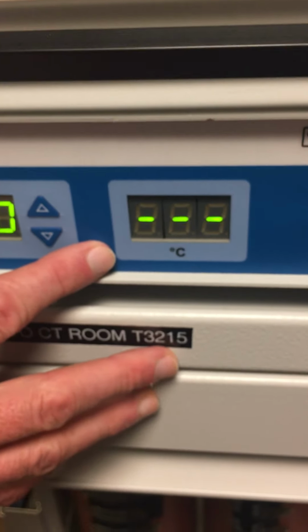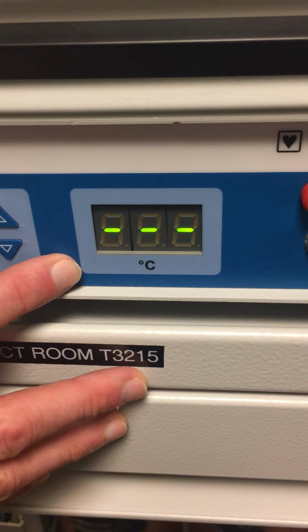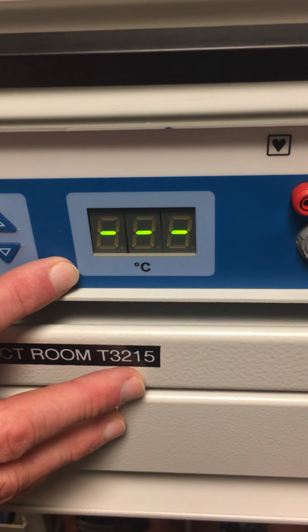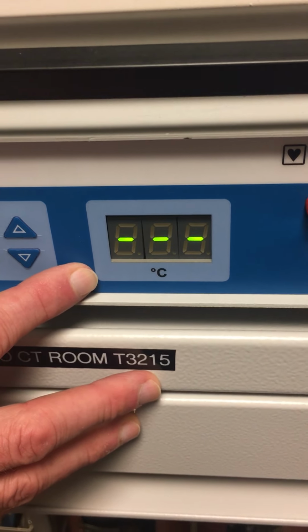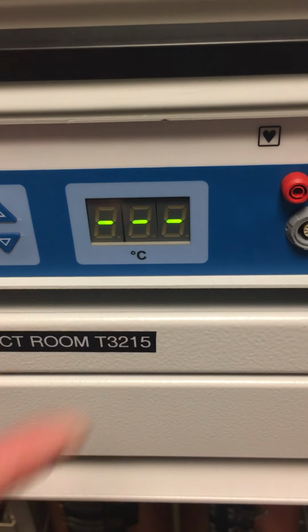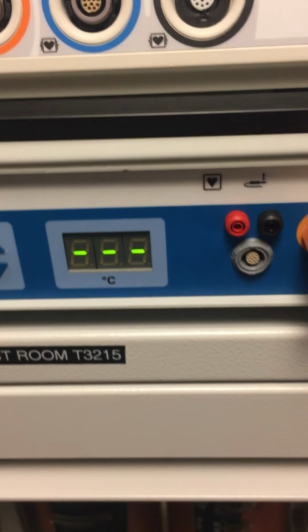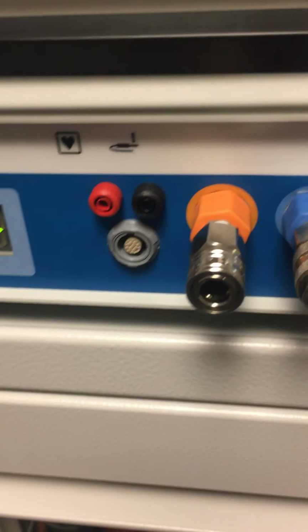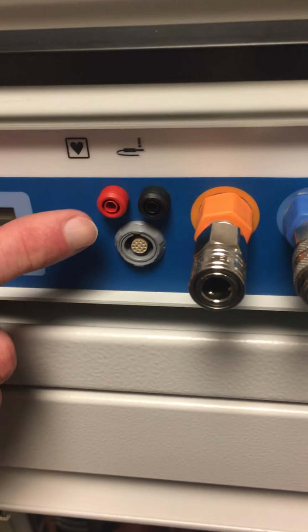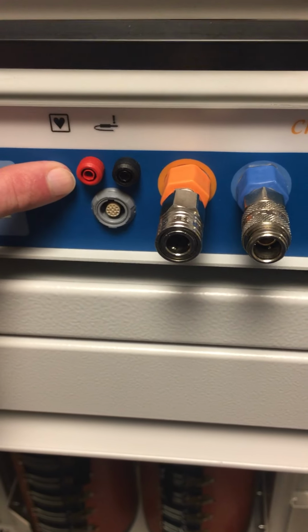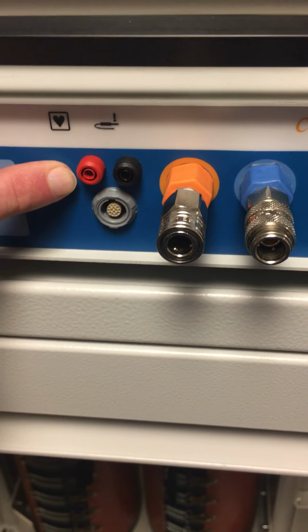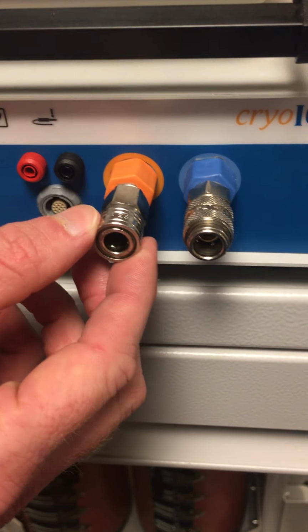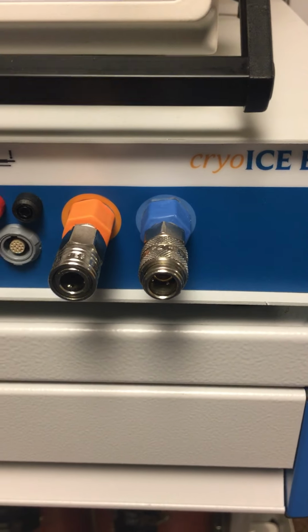Next to that's our temperature gauge. Again, out of our control. Once we go ahead and connect the Cryo Probe, we will start to generate a temperature there. And then obviously when we start the freeze, it will go down to freezing temperatures. From here we have 4 connects that we need to be mindful of. 2 are for temperature, again all color coordinated, and then we have 2 for the Cryo Probe itself. At this point we're going to show you the Cryo Probe.